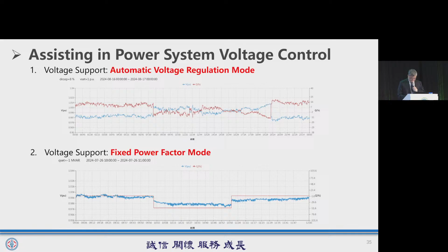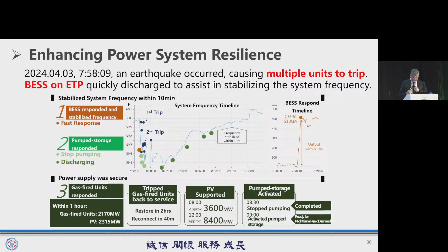Enhancing power system resilience: on April 3rd, 2024, a major earthquake in Hualien caused multiple power units totaling 3.2 gigawatts to trip, dropping system frequency to 59.50 Hertz. The BESS responded almost instantly, discharging 510 megawatts and helping stabilize the grid within 10 minutes. Combined with support from pumped storage and rising solar output, the system recovered quickly and avoided a blackout. This event highlights the critical role of BESS in enhancing power system resilience.